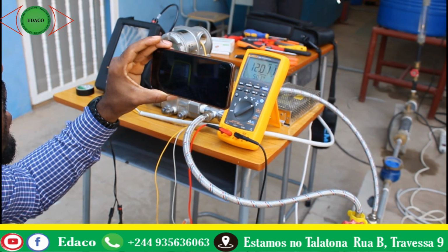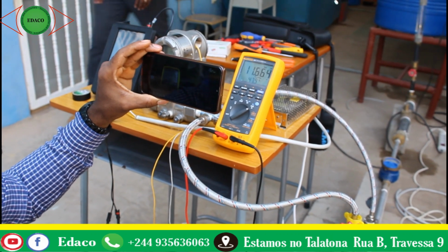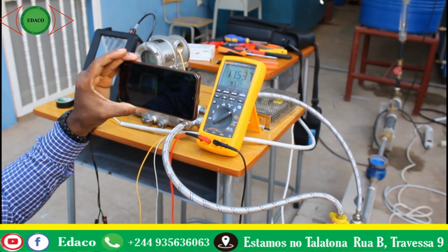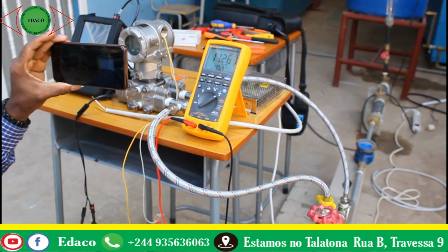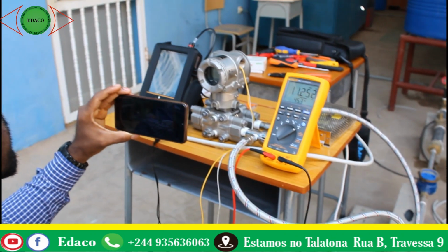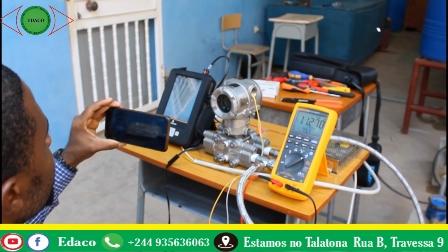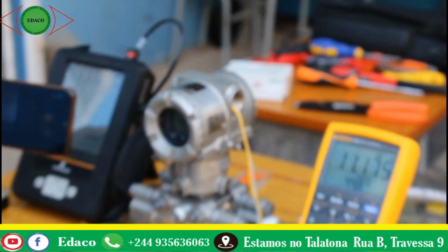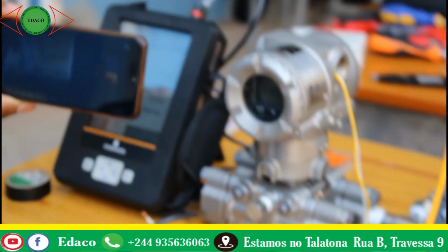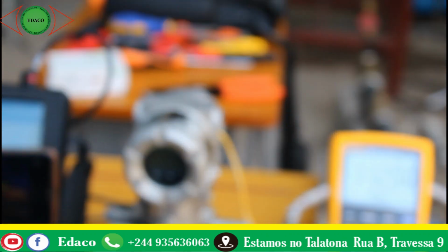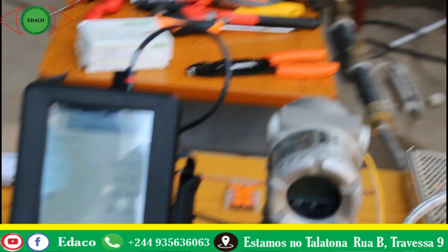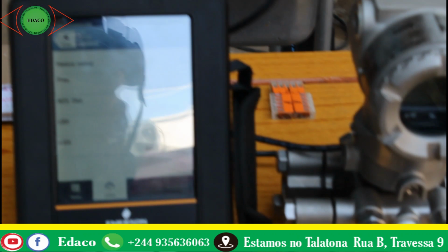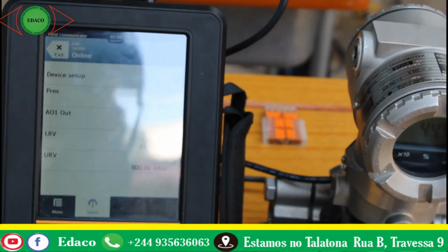We are roughly almost at 50%, and our pressure is now 360 millibars, and the signal is 11.18. So we are roughly at 50%, or at 40%.